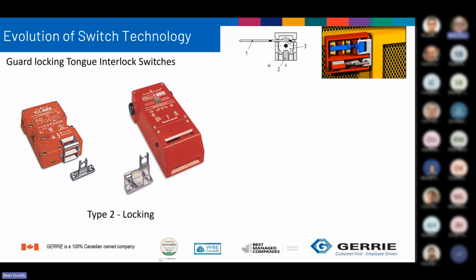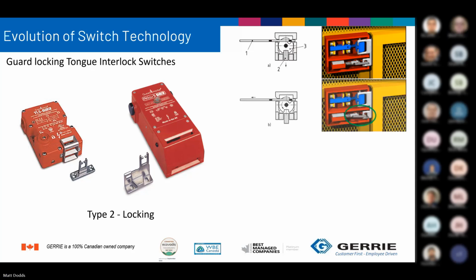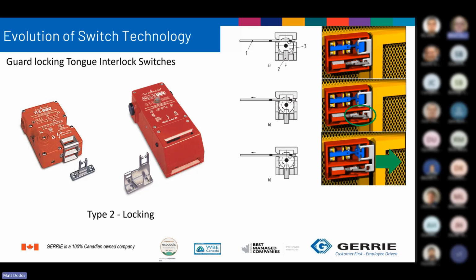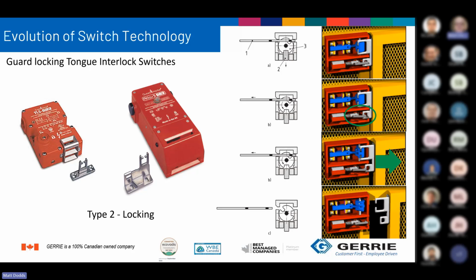So the door is closed and locked. Power is applied, so power to release the actuator. So again, you can see it there. It opens up that little hook mechanism on the actuator. The door starts to open, and then now the door is fully open and the contacts have changed state.